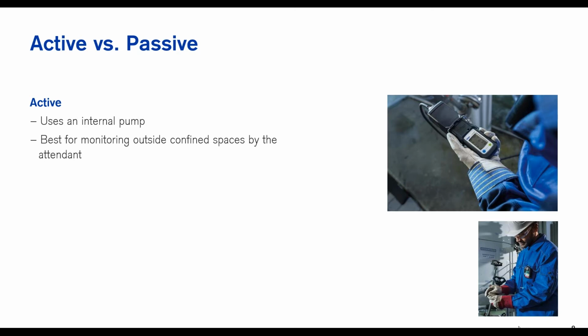Understanding the next bullet point is your response times. It's not as simple as taking that meter out, firing it up, and seeing what it says. You have to understand what that response time is. We'll talk more in a couple slides about T50 and T90 response times, and those are all specific to your meter, specific to the sensor of your meter. You may have a meter that shows a T90 response time of 10 seconds for, say, your oxygen sensor, and 20 seconds for your LEL sensor. They're all different based on what you're actually measuring and the type of meter equipment you have.